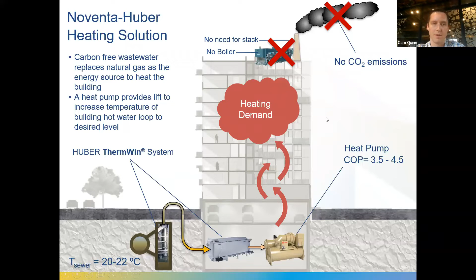All we're doing is switching whether we're tying into the evaporator loop or the condenser loop on the chiller or the heat pump, and providing low-grade hot water to the hospital HVAC system. So again, we're using carbon-free wastewater, which replaces natural gas as the energy source to heat the building, and we use the heat pump to upgrade the temperature of the building hot water loop. And again, if we're talking about efficiencies, in our heating mode, our COP is in the 3.5 to 4.5 range. So compared with the 0.75 to 0.8 of the steam plant, we have a large gain again in efficiency and reducing our energy intensity, which is important.